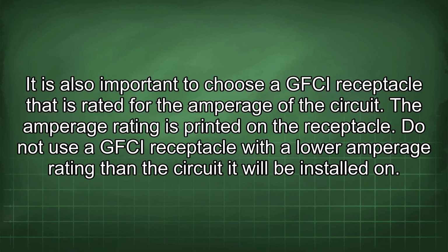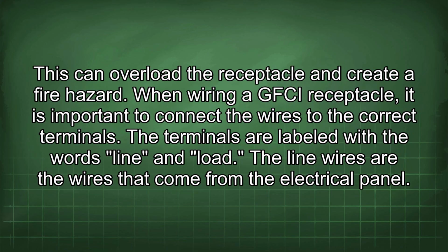It is also important to choose a GFCI receptacle that is rated for the amperage of the circuit. The amperage rating is printed on the receptacle. Do not use a GFCI receptacle with a lower amperage rating than the circuit it will be installed on. This can overload the receptacle and create a fire hazard.